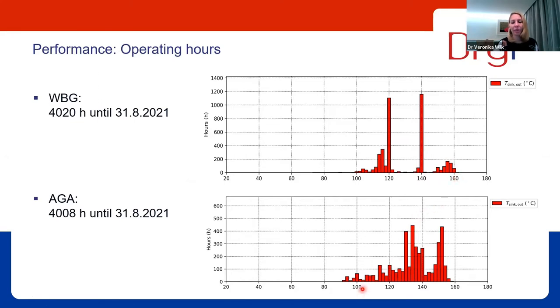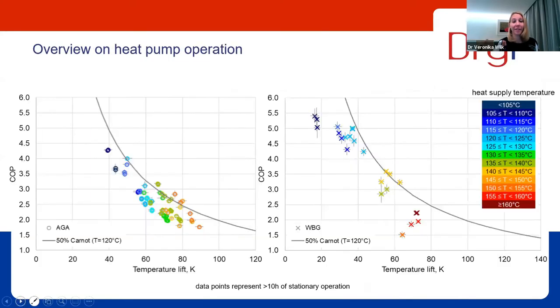At the Agrana installation, we've tested many different heat supply temperatures between 100 and 160. We have two peaks here also, lots of operation around 135 and 155. And this is how it turns out in terms of COP. So the COP is typically the most interesting value to characterize heat pump operation. So the COP is the ratio of the heat that is provided by the heat pump divided by the amount of electricity that is consumed.